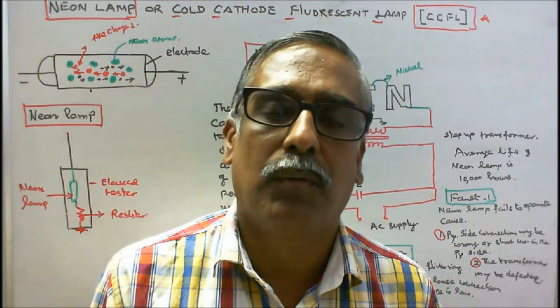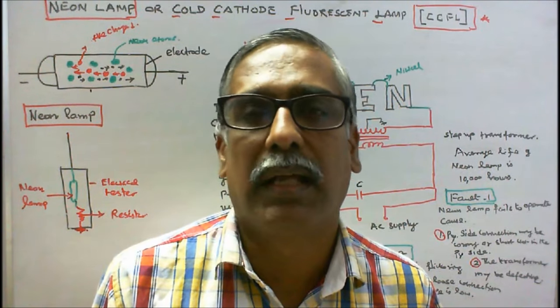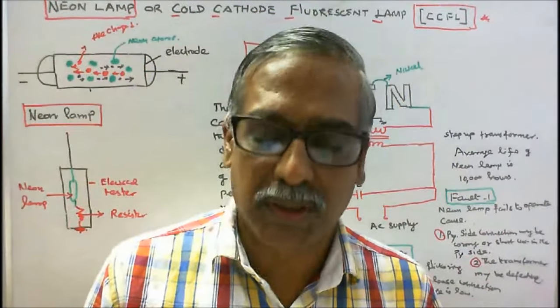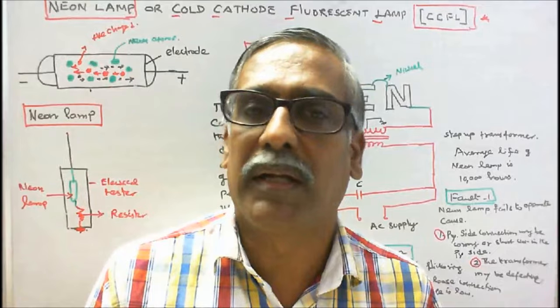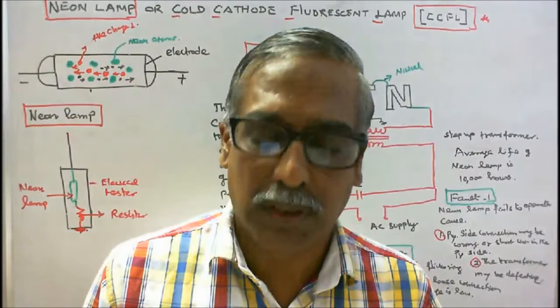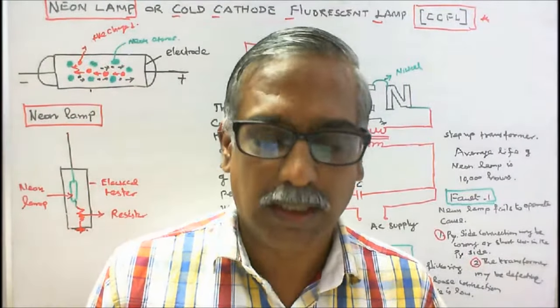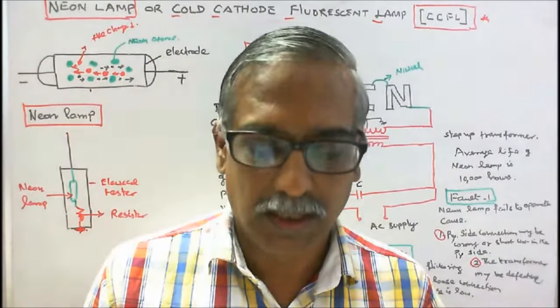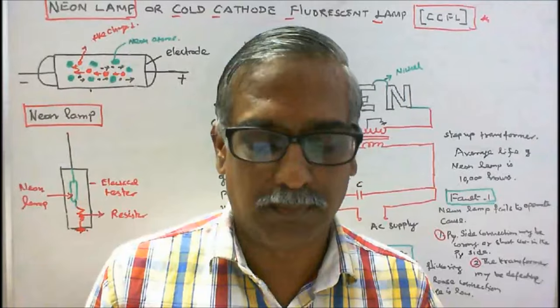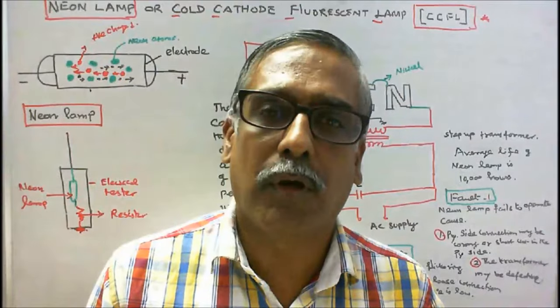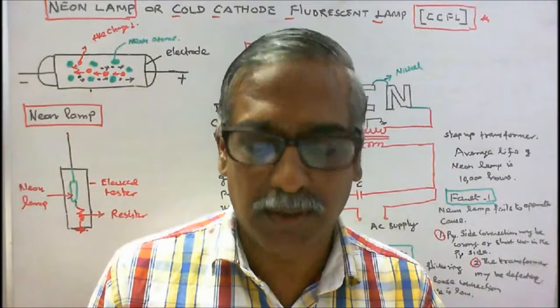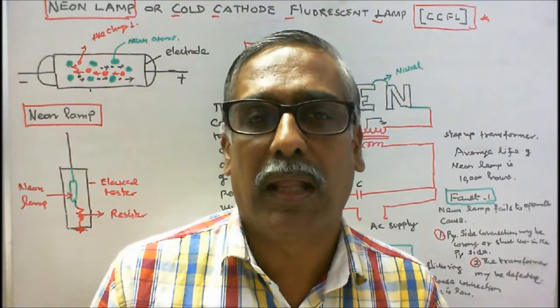There are two types of cold cathode fluorescent lamps: neon lamps and neon tubes. Neon lamps are used in indicators, night lamps, and polarity testers. They are generally of five watts. They consist of a glass bulb filled with neon gas and give orange-pink light. The electrodes are made of iron, steel, or copper, spaced a few millimeters apart. The lamp efficacy lies between 15 to 40 lumens per watt. A series resistor is connected in series to control the magnitude of current — for example, in an electrical tester.